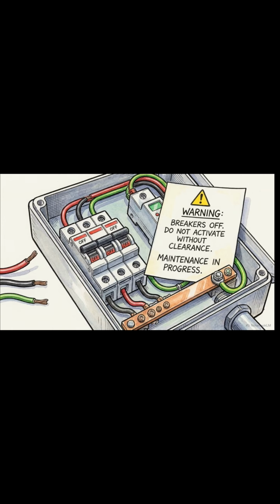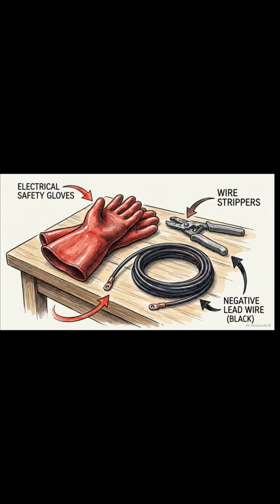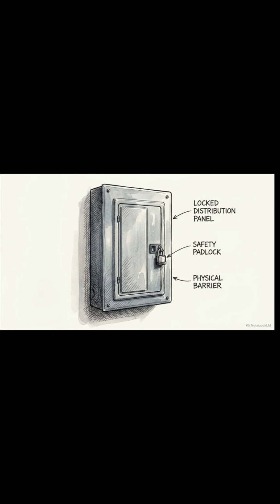Just like before, verify that every single AC breaker inside this distribution box remains firmly locked in the off position while you work. You are operating in a vulnerable transition zone here. You are safely changing the electrical format, but keeping the rest of the home's grid completely walled off until the conversion is secure. With the primary power lines run, we have to establish our fail-safes.